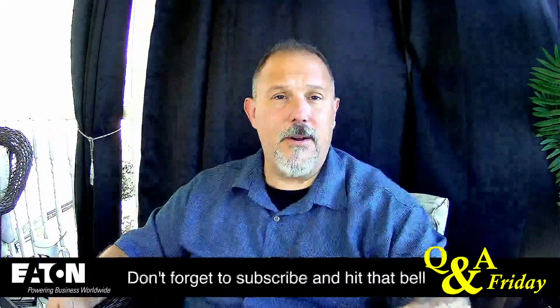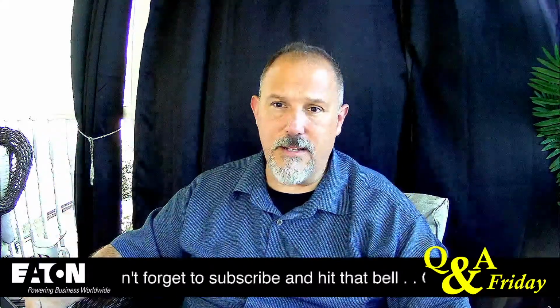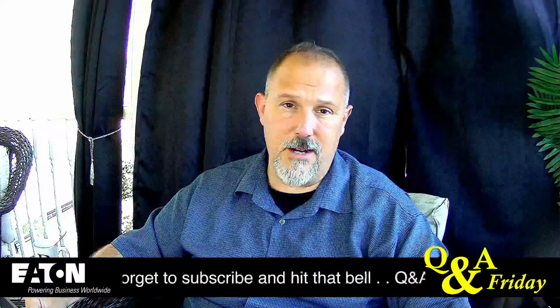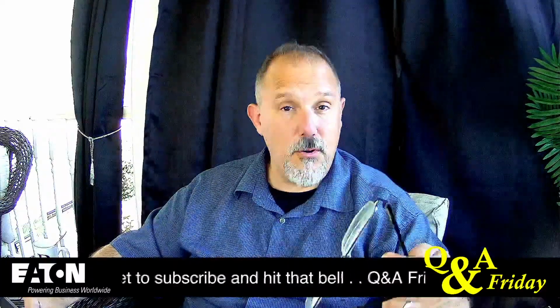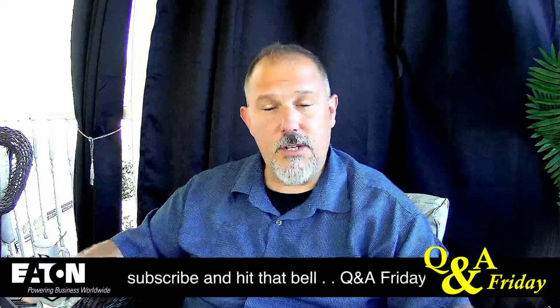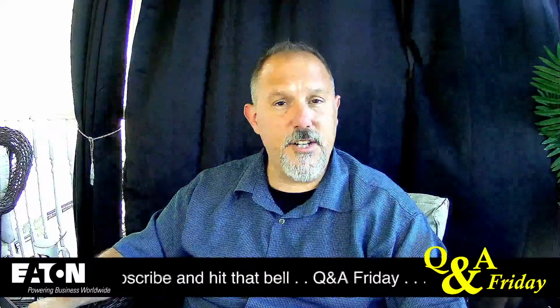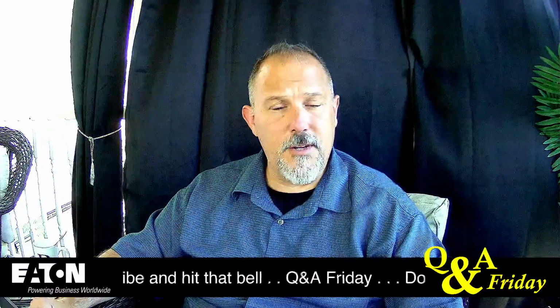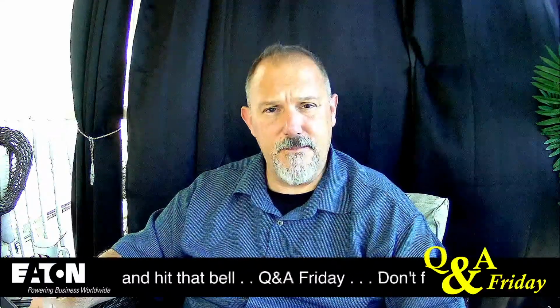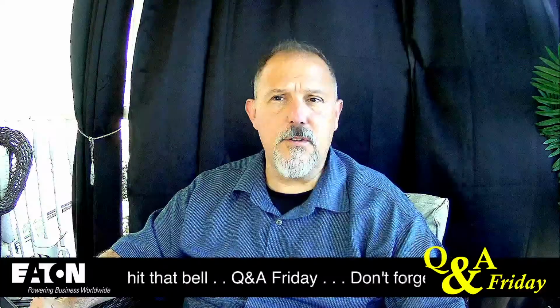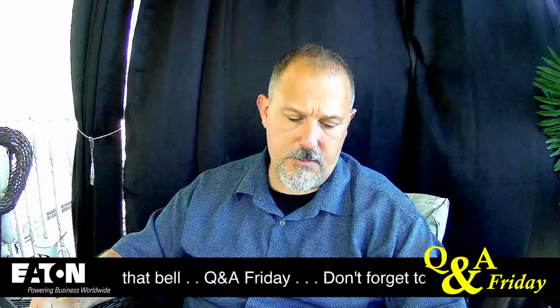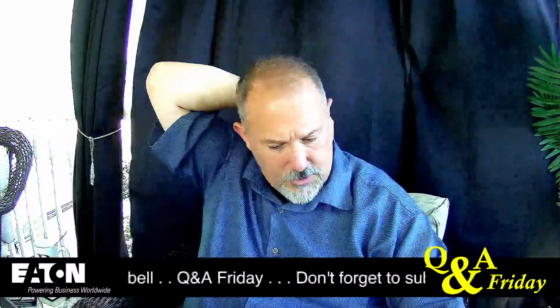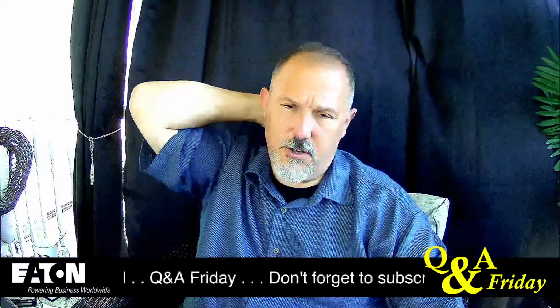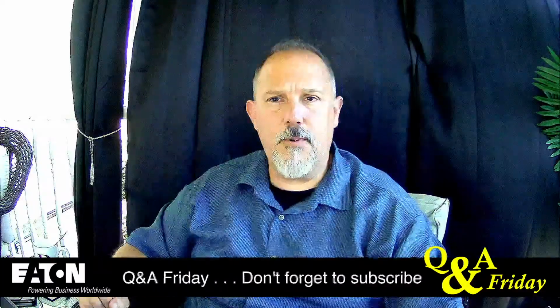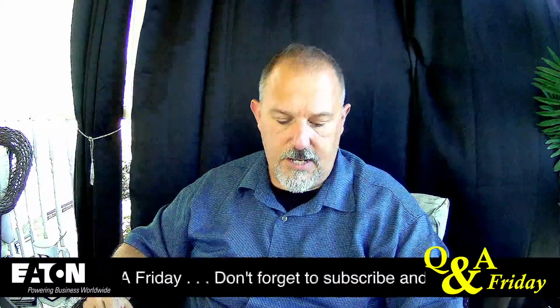Because even if you're in a barrier, if that barrier is not listed for line side propagation, well, then you've got issues there, because you can't make the claim. You can say this is what my engineering judgment is, but engineering judgment only gets you so far on a witness stand, right? So you've got to be very careful, especially when it comes to arc flash. But your conservative nature, Mr. D, of line side propagation is safe.